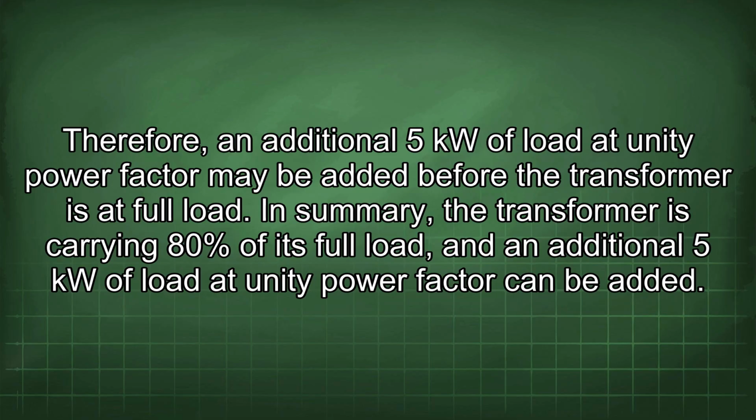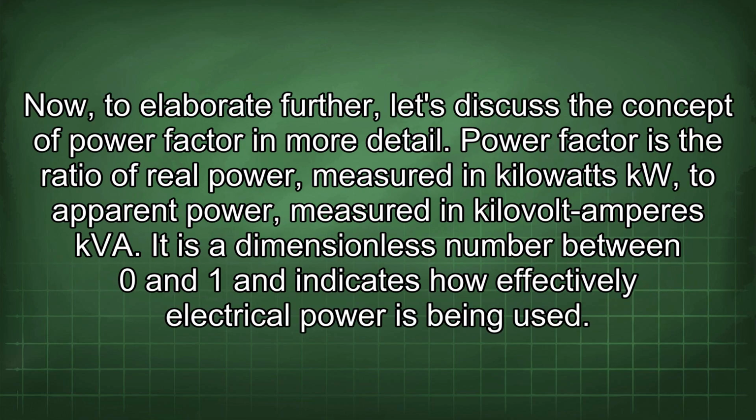Therefore, an additional 5 kW of load at unity power factor may be added before the transformer is at full load. In summary, the transformer is carrying 80% of its full load, and an additional 5 kW of load at unity power factor can be added. Now, to elaborate further, let's discuss the concept of power factor in more detail.